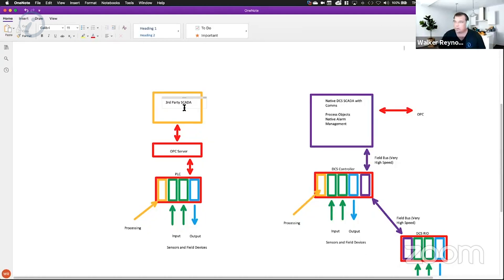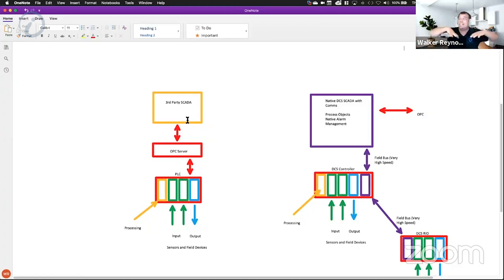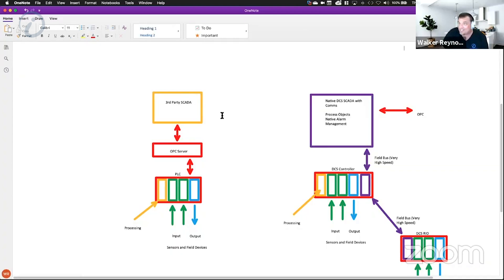When you install Wonderware, Ignition, or any of the third-party SCADA platforms, they are blank — all you have is a canvas to create a SCADA application. SCADA is supervisory control and data acquisition; it's where you manage a plant remotely. SCADA is HMI on steroids. HMI is generally unique to a specific process or a particular line. SCADA aggregates all of that into one interface where you're managing all of your alarms, controlling the process, turning it on or off, and adjusting setpoints. But when that SCADA software gets installed, it's just a blank canvas — just an IDE.